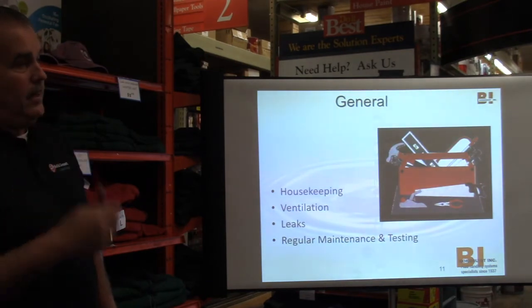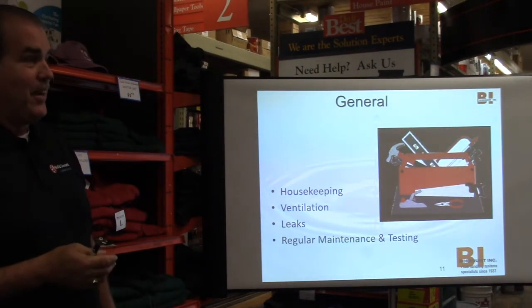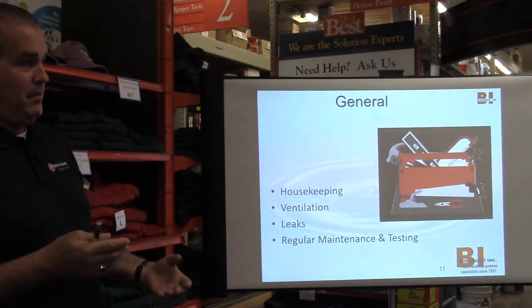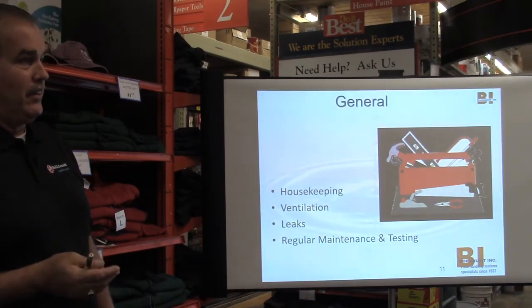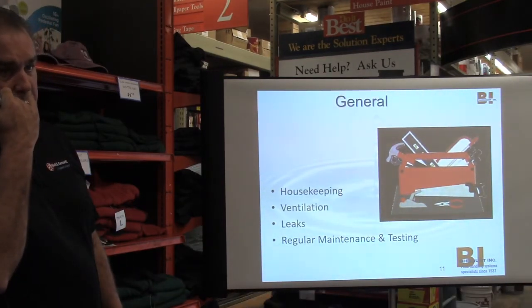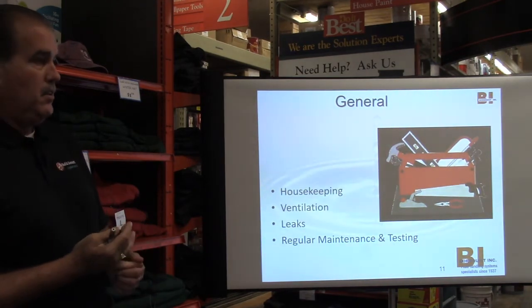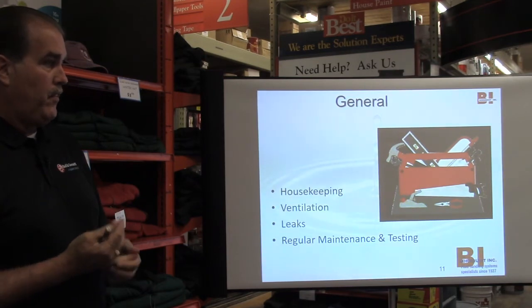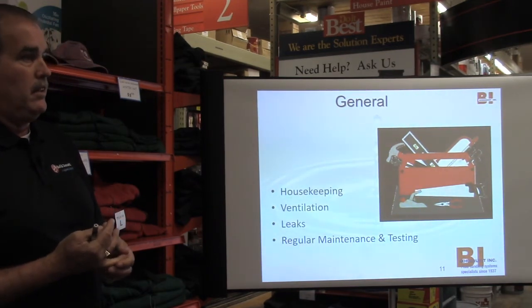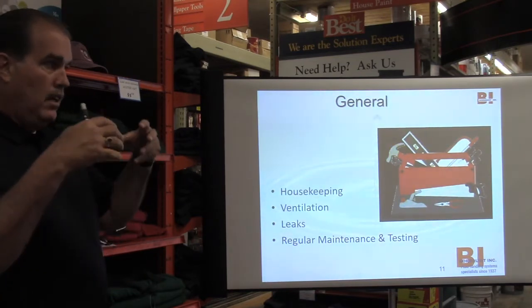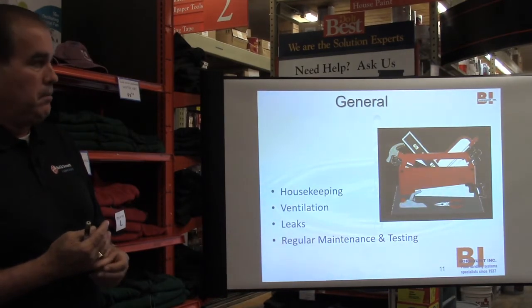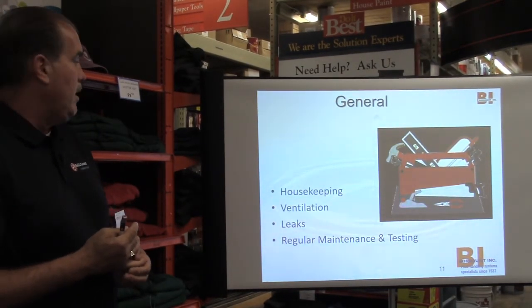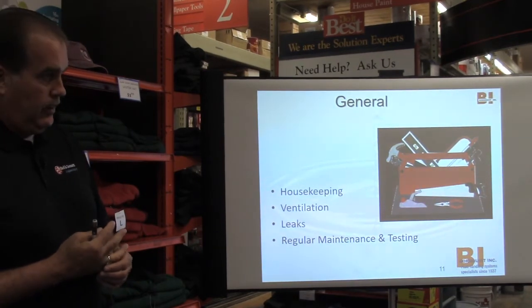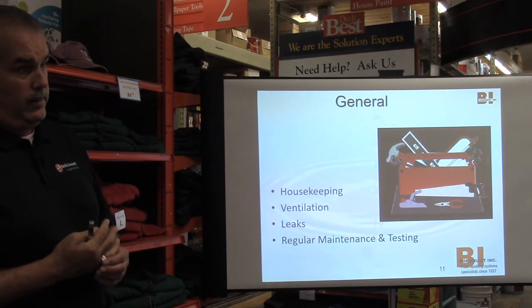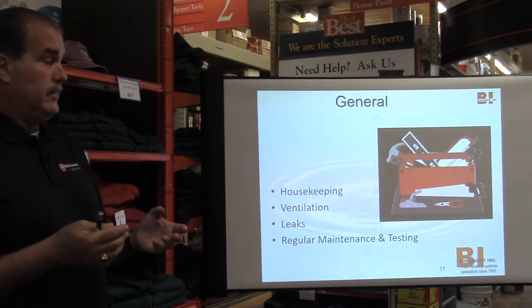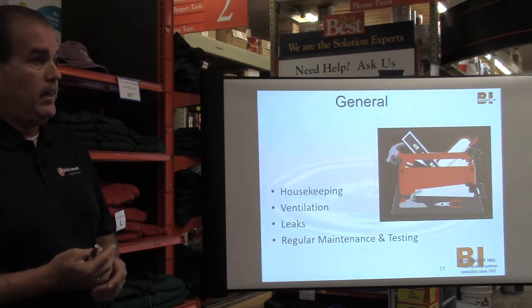Leaks. Well, hot water systems aren't supposed to leak. Steam systems naturally leak from venting, but they're not supposed to leak either. Yeah, okay. They return, everything leaks, so you want to try to find them if you can. One, you're going to be using a lot more makeup water. And the problem with freshwater makeup is it brings in all the chemicals that come with it, particularly calcium, which then coats and covers everything and sticks to everything. That can plug up pipes, it can plug up heat exchangers, it can cause a whole lot of problems. If you suspect you have a leak, you can put a water meter on your system to see. It's a little expensive, but it's probably about the only way to find out whether or not you truly have a leak.